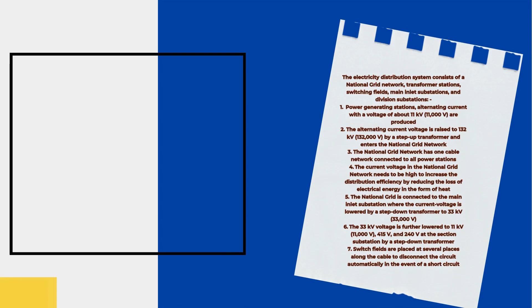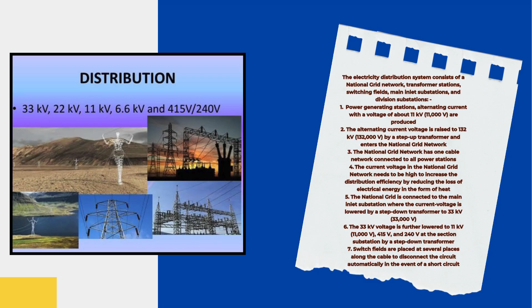At power generating stations, alternating current with a voltage of about 11 kilovolts, that is 11,000 volts, is produced. Then the alternating current voltage is raised to 132 kilovolts by a step-up transformer and enters the national grid network. The national grid network has one cable network connected to all power stations, and the current voltage in the national grid network needs to be high to increase distribution efficiency by reducing the loss of electrical energy in the form of heat.